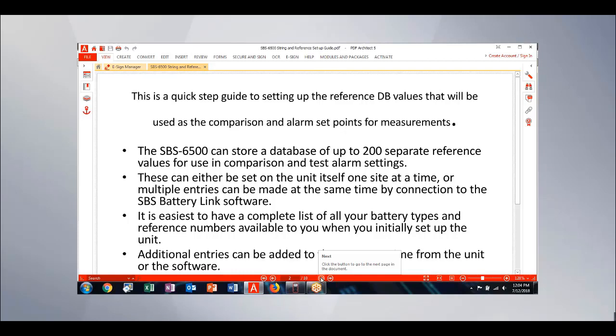So the 6500 can store a database of up to 200 separate reference values. So this would be my battery models and manufacturers, and then all of the alarm thresholds for low voltage, low or high internal resistance, temperature alarms. Those all get set up in that database ahead of time. And then as I set up my strings or my locations that I'm going to be taking measurements at, I just select the appropriate battery installed in that location from that database entry.